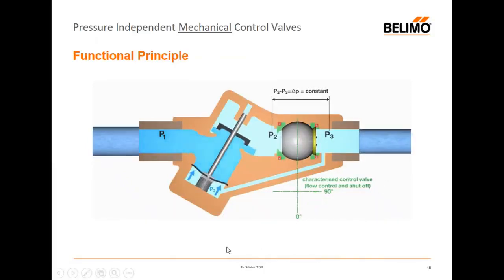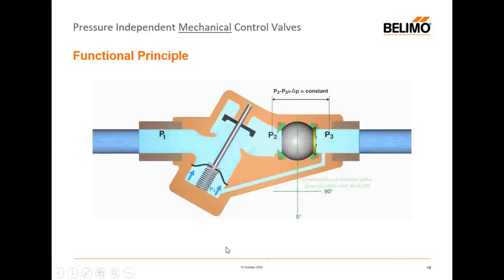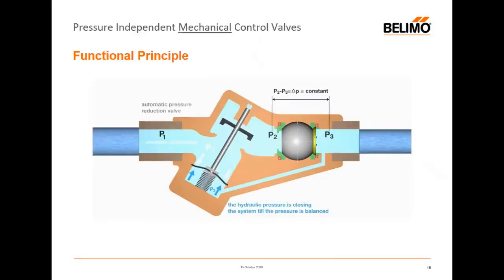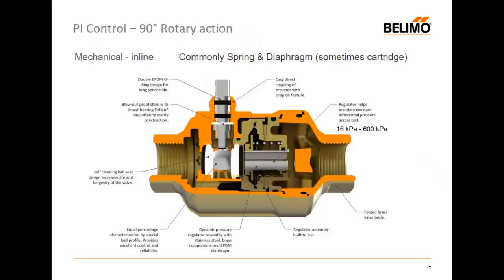And so it's understood that all mechanical PI valves operate in this way. This is an oblique pattern. We have inline, like this valve. This is an inline version of the same valve. And you can see the internal complexity. We've got a spring here, and we've got a diaphragm, we've got a seat, and we've got the control element here. So we're maintaining a constant delta P here.